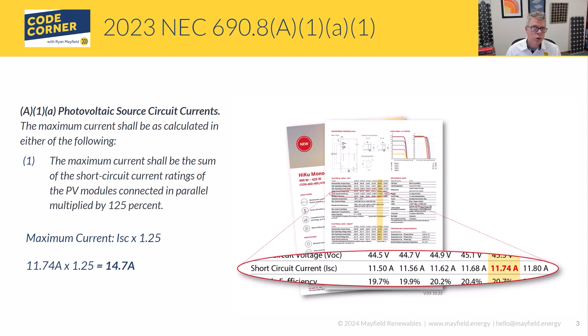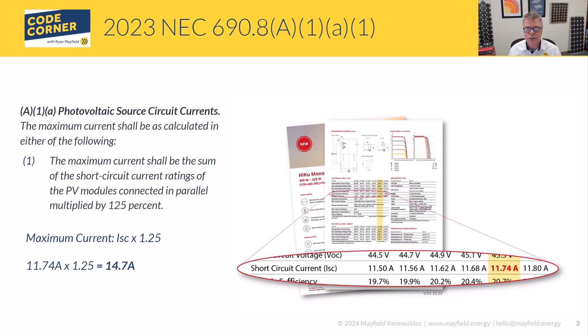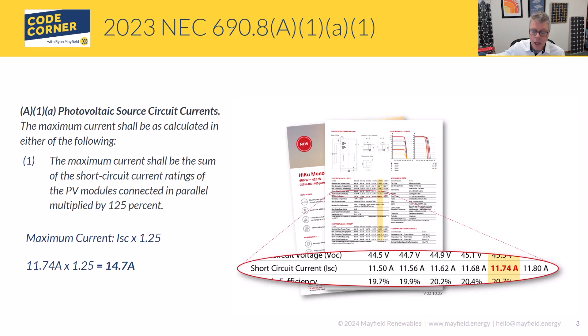That 125% factor takes into account that our PV modules will put out as much current as the sun allows. PV modules without any electronic device on their output are going to put out whatever the sun permits. Edge of cloud effect, reflectance from snow, and similar conditions will potentially increase the current the modules produce. So that correction factor says 125% above standard test conditions defines our maximum current. That term 'maximum current' will show up again later in 690.8B and in 690.9 for overcurrent protection.